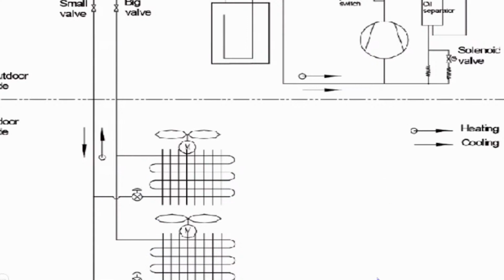So if you've got 4 heads, look at the data on each coil. Look at the EEV step. Let's say that thing's open at 150 steps, and that inlet temperature sensor is basically room temperature. What does that tell you? I'm not getting any refrigerant into that coil. Could I have a bad EEV? Yeah, it's likely. Or a restricted strainer.